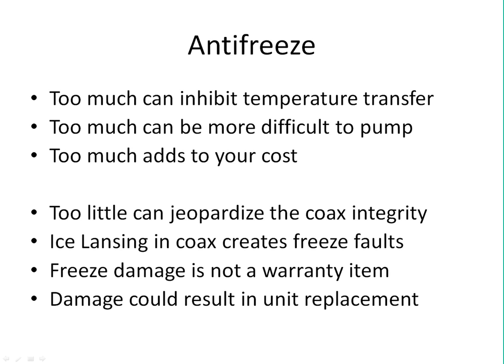Let's talk a little bit about too little antifreeze. Too little can jeopardize the coax integrity. In other words, if you start to swell and/or freeze that heat exchanger, you're going to have performance issues. If you don't have enough antifreeze in there, as you tax your loop and the temperature of the solution drops, you can actually start to create what we call ice lancing. And that is ice particles building up. They'll actually start to choke off or restrict the flow, which slows the flow rate down, which means you're going to ice up a little quicker because it's lingering longer with the refrigerant.